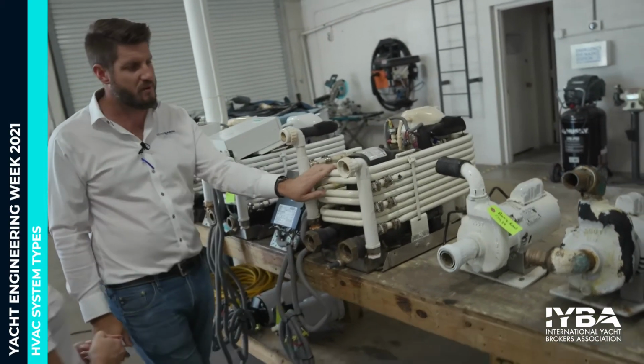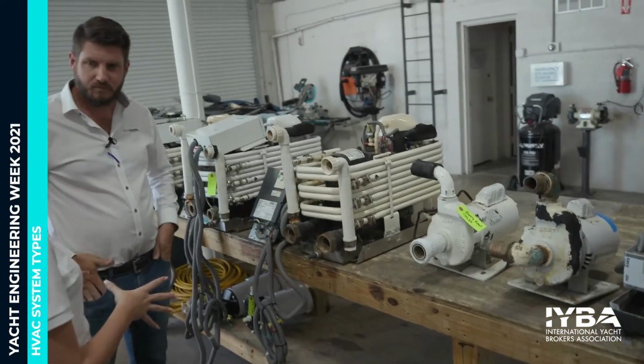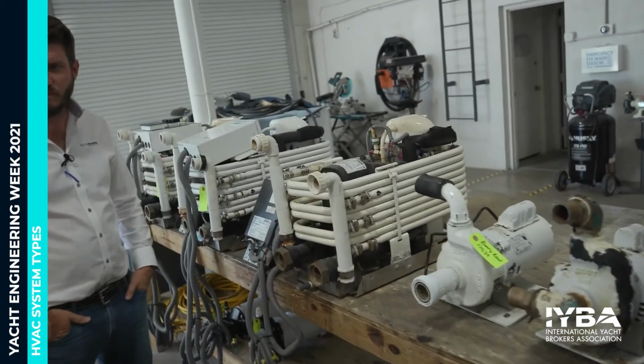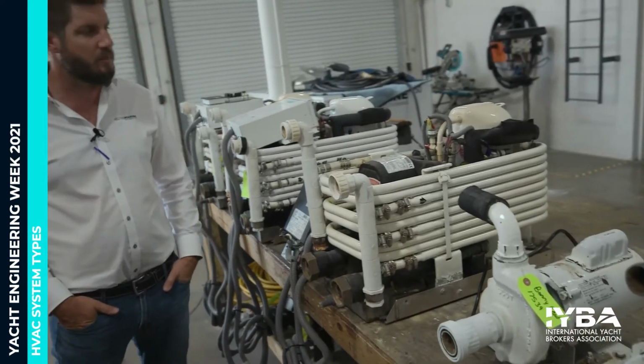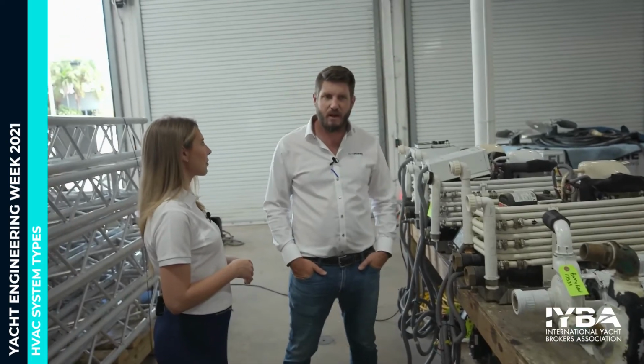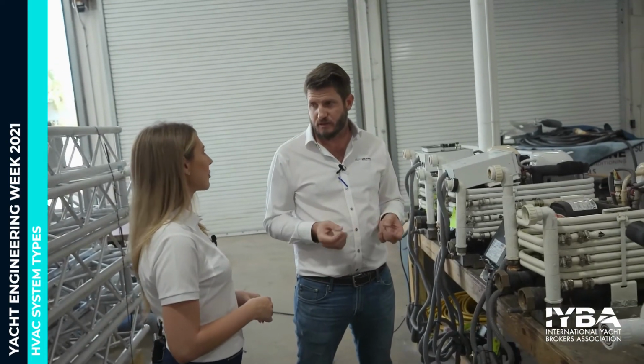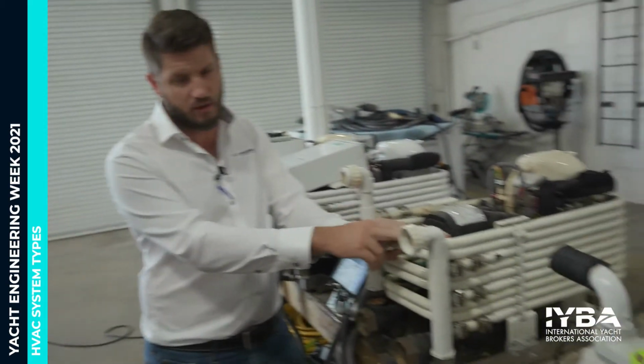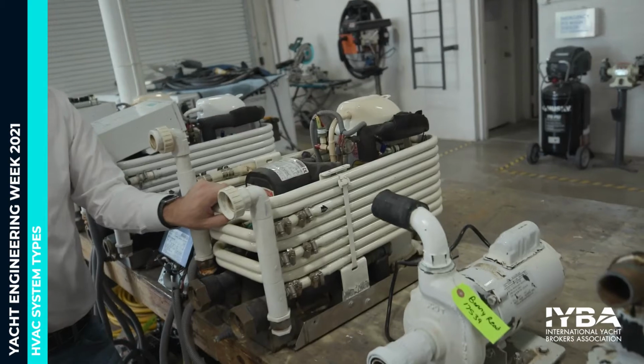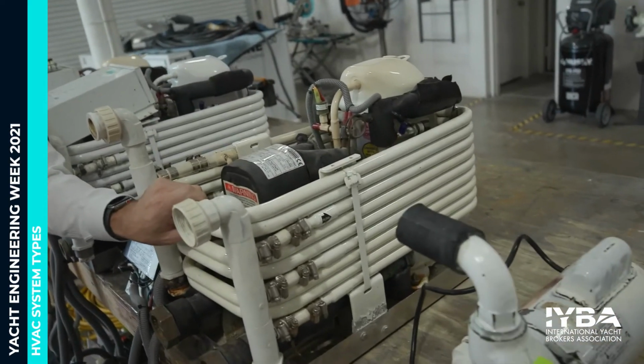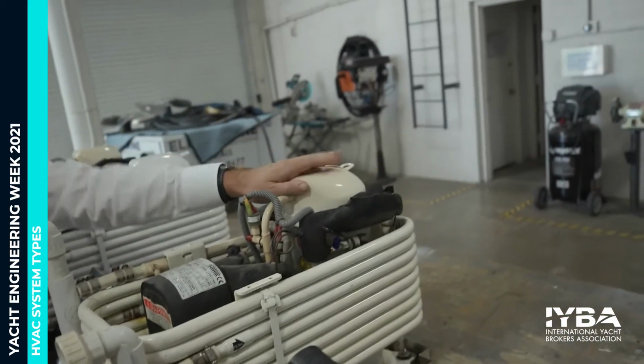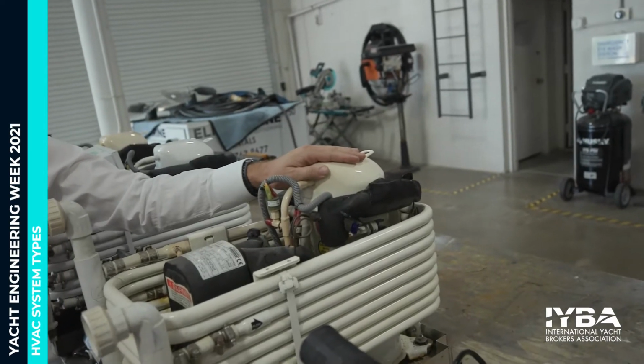A lot of moving parts, and I'm still trying to grasp this, so let's break it down a little bit more piece by piece. Let's go back to the refrigerant circle. So what exactly is the refrigerant itself? The refrigerant is a chemical that has a pressure-temperature relationship. At any given pressure, there's a guaranteed temperature that the refrigerant will be. So inside of this refrigeration circuit, there's no air, there's no water, there's no moisture, it's just refrigerant. And what the compressor is doing is just recirculating that refrigerant through those four major components.